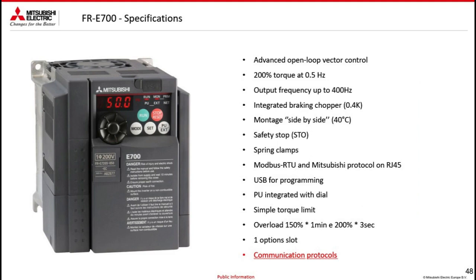As regards the characteristics here too, we have the possibility of vectorial but advanced control. By open loop, we mean without encoder. It is possible to reach 200% torque at 0.5 Hz. The output frequency reaches 400 Hz. There is an integrated 0.4 kilowatt braking chopper, 40-degree side-by-side mounting, spring terminals, Modbus RTU and protocol Mitsubishi RJ45, and there is USB for programming.